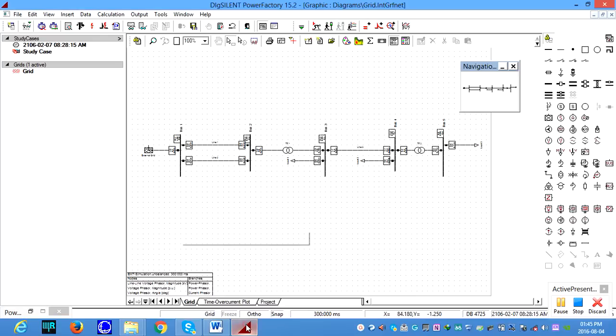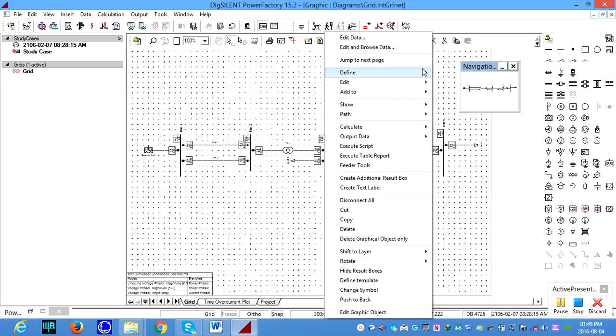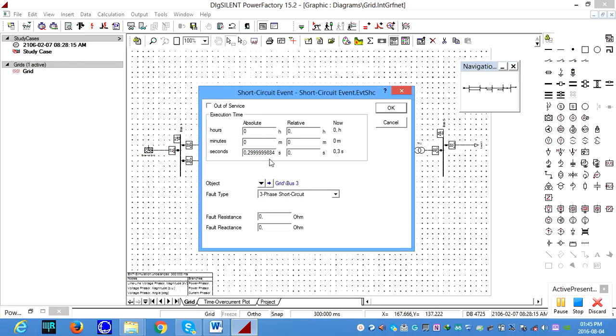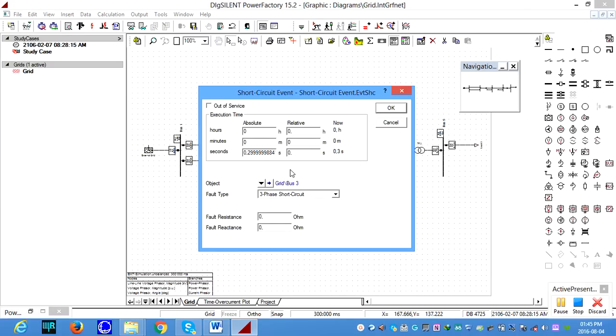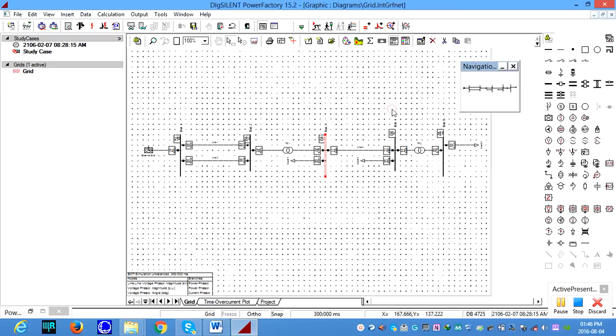So to do that, first we need to define. Right click the bus, go to define, and then you can go for the short circuit. Okay, so we need to create a short circuit, a three phase short circuit, and we can say what time it is supposed to be. Let's say 0.1 seconds. From 0 to 0.1 second there is no fault, but at 0.1 seconds we create a three phase short circuit.